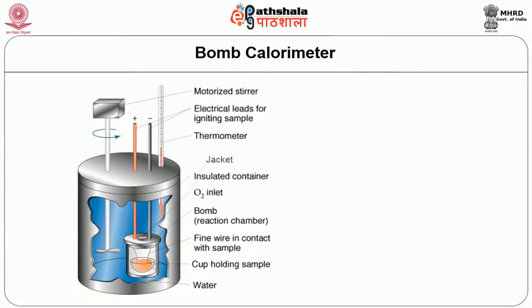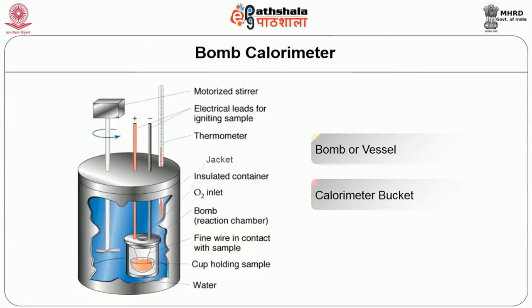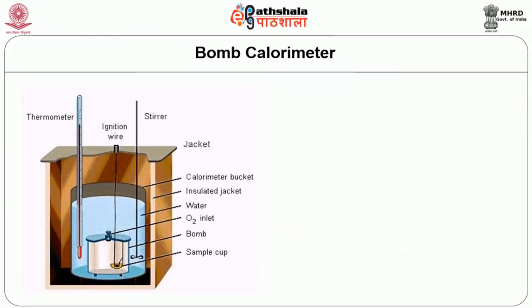The oxygen bomb calorimeter consists of three essential parts: number one, the bomb or vessel in which the combustible material is burned; the calorimeter bucket or water container holding a measured quantity of water in which the bomb is immersed; and the jacket for protecting the calorimeter bucket from the effect of variation in room temperature.